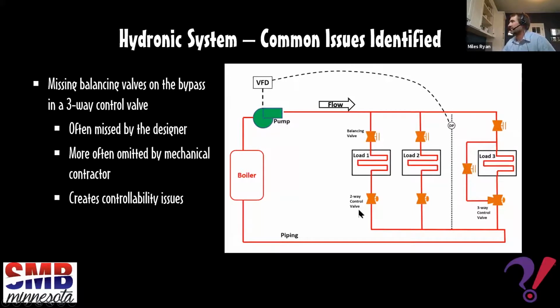On a variable speed system, most of the control valves at the loads are going to be two-way control valves, because when they start to close flow, that's going to drive up the differential pressure, and then the pump will know to slow down. It's important that they're all two-way control valves, or most of them. However, oftentimes you're going to have one or a couple three-way control valves in the system, because if none of these loads were calling for flow, you have to give a path for the pump to push flow through. So you have to give them this bypass pipe right here.